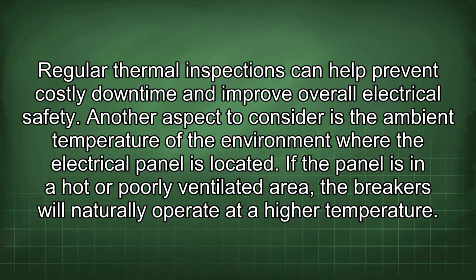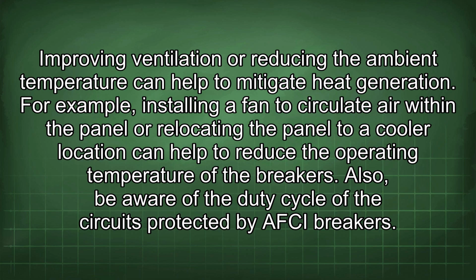Another aspect to consider is the ambient temperature of the environment where the electrical panel is located. If the panel is in a hot or poorly ventilated area, the breakers will naturally operate at a higher temperature. Improving ventilation or reducing the ambient temperature can help to mitigate heat generation. For example, installing a fan to circulate air within the panel or relocating the panel to a cooler location can help to reduce the operating temperature of the breakers.